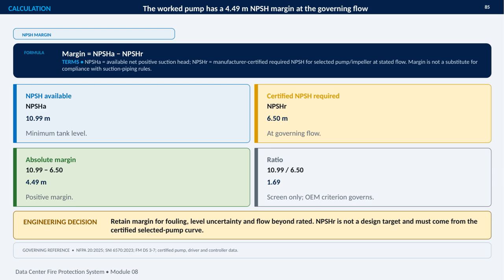From an engineering standpoint, we retain this margin to allow for fouling, uncertainty in tank level, and flow beyond the rated condition. It is also important not to treat NPSHR as a design target. It must come from the certified selected pump curve. Finally, a positive NPSH margin does not replace compliance with suction piping requirements. The governing references include NFPA 20:2025, SNI 6570:2023, FM Data Sheet 3-7, and the certified pump, driver, and controller data.